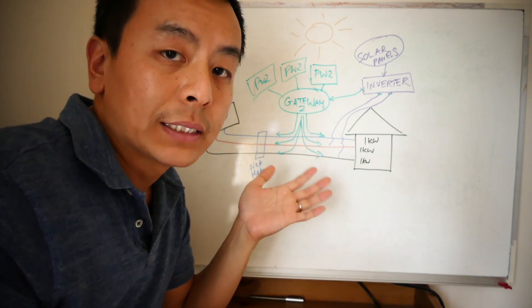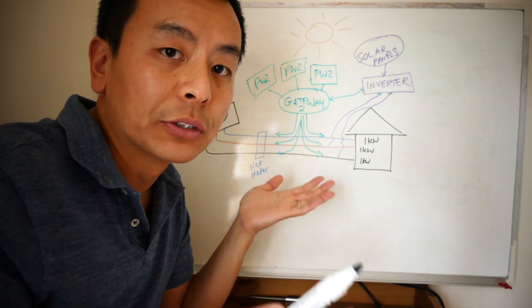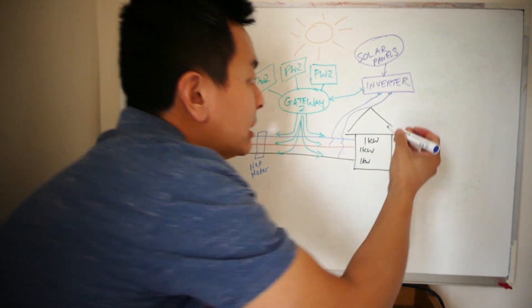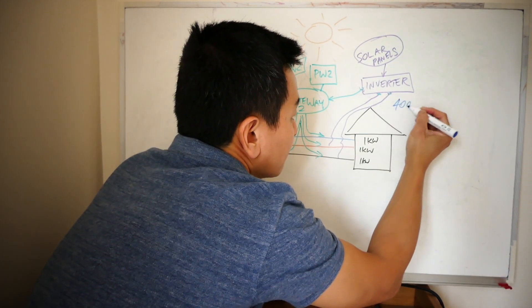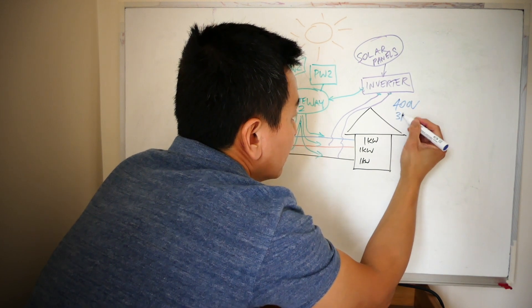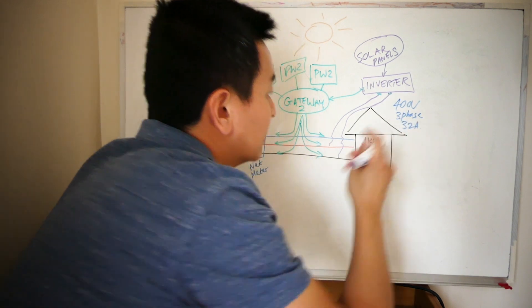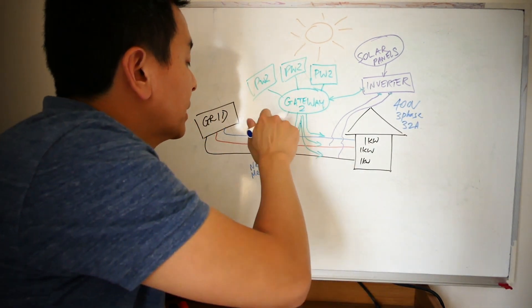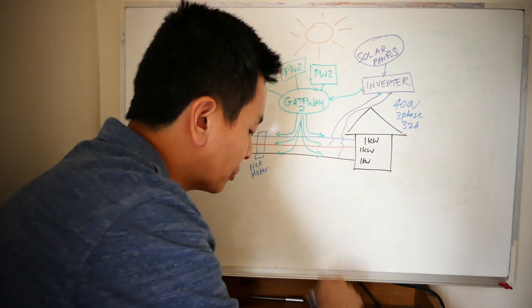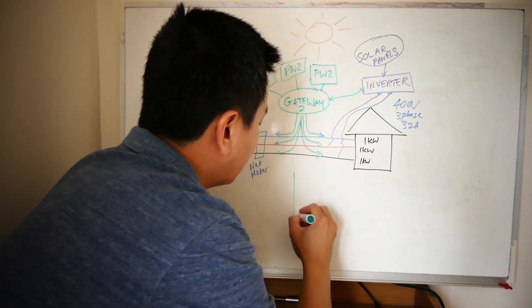At three-phase, presumably at 32 amps per phase. So in that case, that's impossible, because the Powerwall 2 is AC coupled, and what do I mean by that?